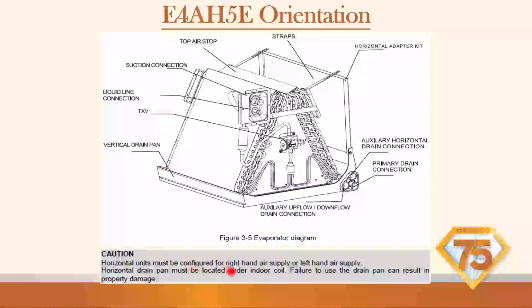Horizontal units must be configured for right-hand air supply or left-hand air supply. Horizontal drain pan must be located under indoor coil. Failure to use the drain pan can result in property damage. Well, I hope everybody knows that. Make sure your drain pan, if you have to swap it to the horizontal, here's our horizontal drain pan. Make sure that's on the bottom of the unit to collect that moisture.